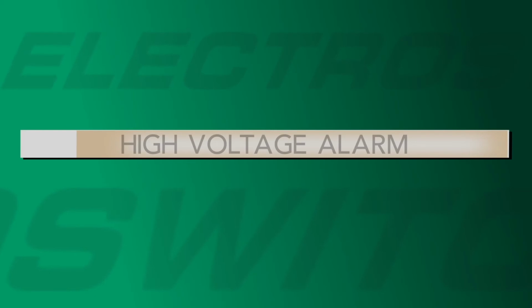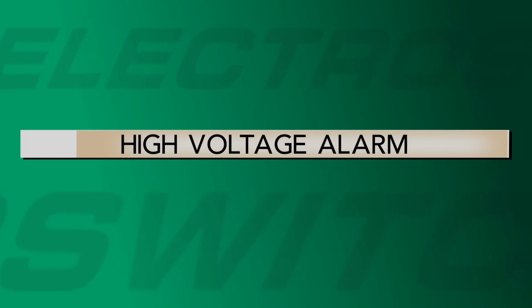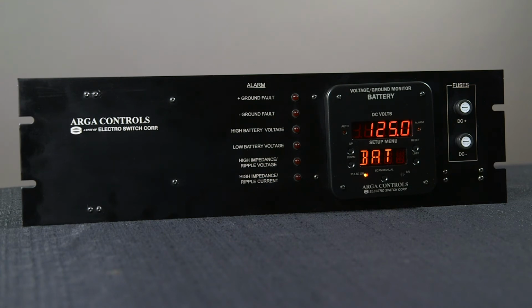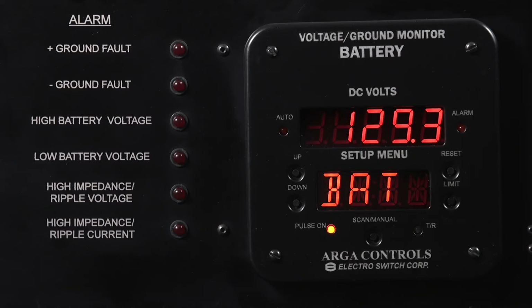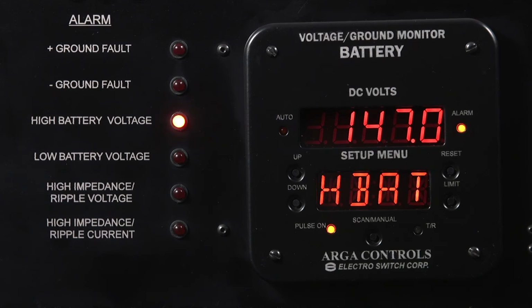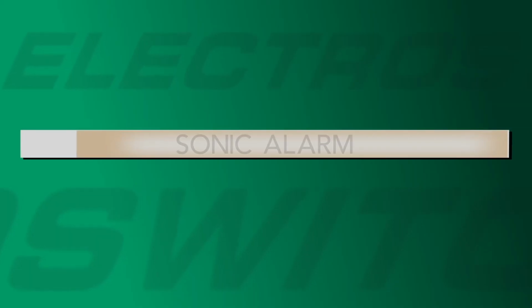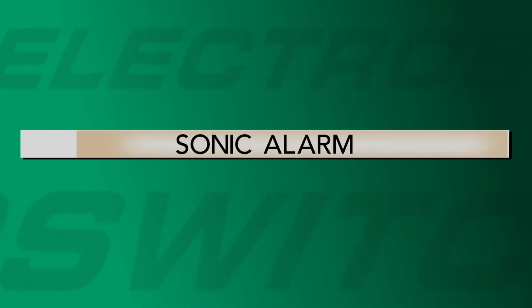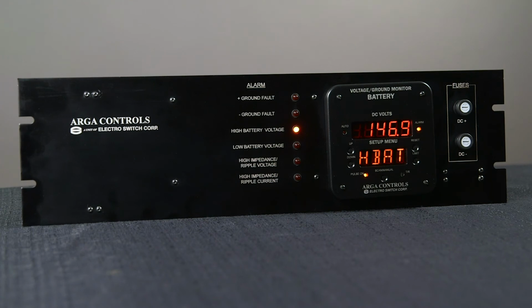Now that you know what these settings are, let me demonstrate what happens as the voltage is increased to the high voltage alarm by increasing the voltage to 145 volts DC. You observe that battery voltage is increasing on the meter indication. When I reach 145 volts DC, an alarm LED on the top right area of the battery monitor will activate, and subsequently, a corresponding high voltage alarm LED will illuminate on alarm outputs to the left of the meter for the rack-mounted battery monitor. At the same time, if I have the sonic alarm enabled, it will provide an audible alarm which can be turned on or off during the initial setup for the monitor.